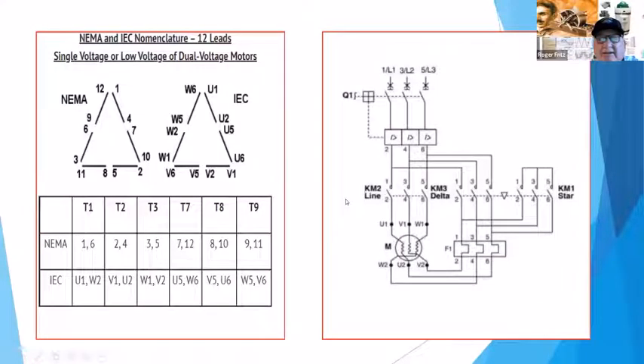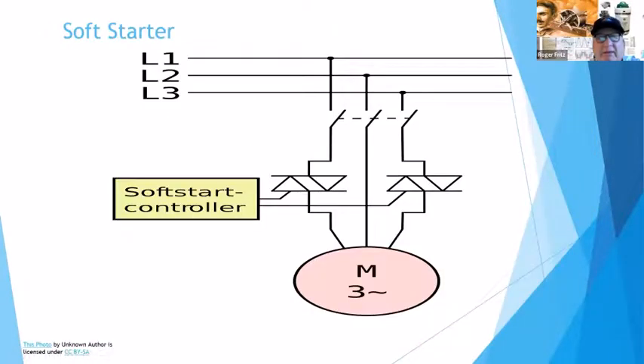Then they rotated, and they found out they needed more torque out of the motors. So they ended up going to Y delta start, which was basically connecting the motor leads so that the voltage drop across the coils was less. So like a 480 volt motor would put 277 volts across with the way they had connected it, and then shift it afterwards, back to across the line, and give it full 480, and that would give it full torque and power. That was the main focus. So that's what was done, definitely prior to the inverter technology that's been built.